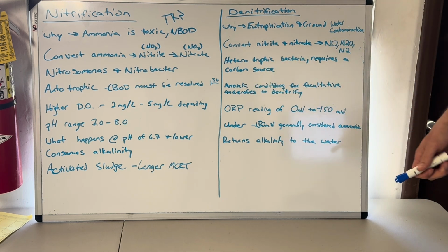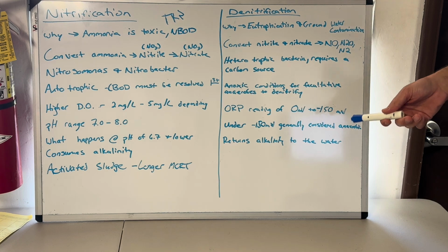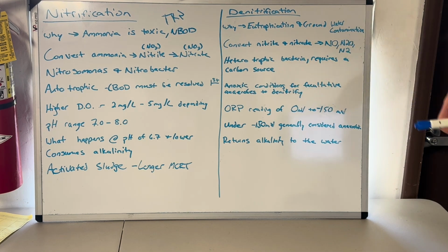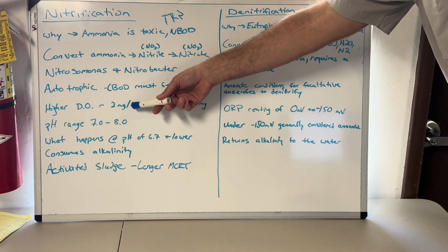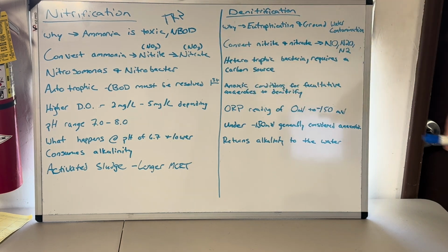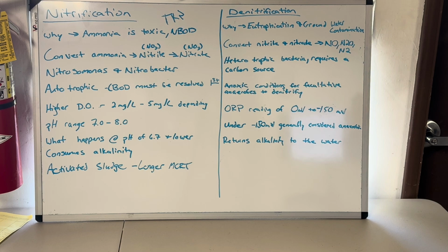Okay, this is anoxic. Well, how do we measure how do we measure our anoxic zone if our dissolved oxygen probe or sensor, or whatever you call it, only goes to 0? And then now I don't know what's going on because anoxic is without dissolved oxygen. Enter the oxidation reduction potential sensor. I love these. I've heard a lot of operators complain about them. I like them. They work for me.